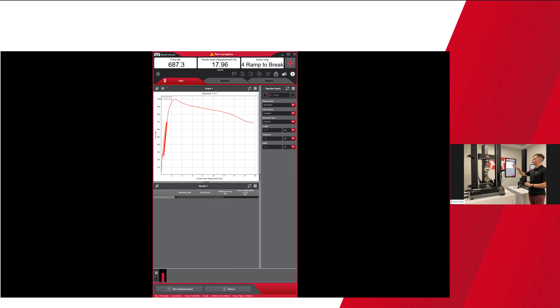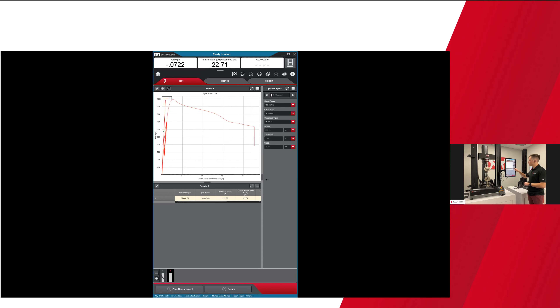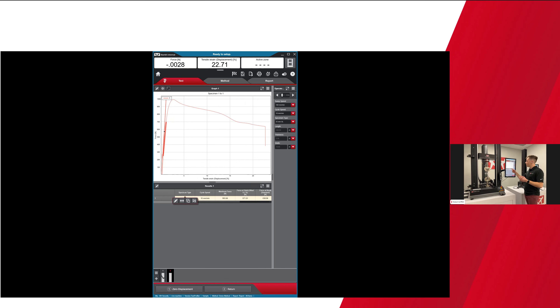The force keeps increasing with each cycle to 700 newtons as we keep stressing the material — something you can always learn about material behavior with Test Profiler. At this point we're moving at the faster ramp speed and running to break. The test shows a live force versus strain curve, and then results populate in the results table. The results table is configurable to include whatever you need to report out to internal customers, external customers, or regulatory agencies. I have specimen type, cycle speed, maximum force, force at yield, break force, max strain, and a modulus calculation.